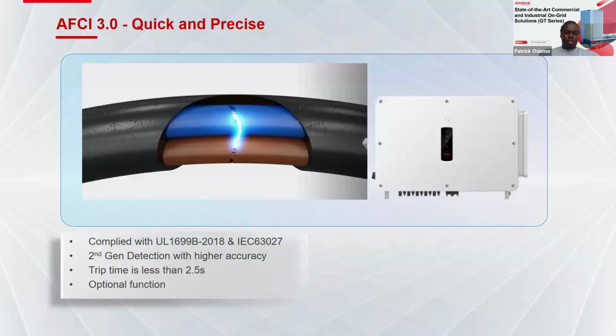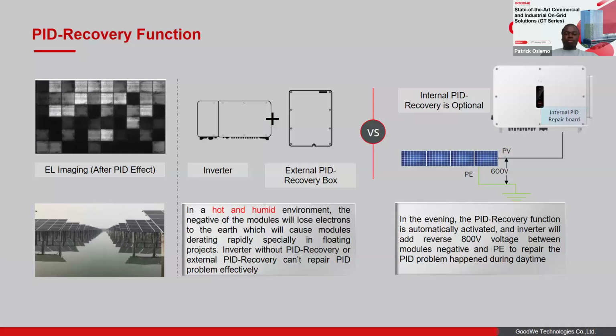Arc fault circuit interruption. Up to 200 meters, response time is very short. So be assured that in case you have loose connections on the roof, which lead to arcs, or even punctured cables on the roof, which lead to arcs, the inverter itself will sense these arcs up to 200 meters away, go to standby and alert you that we have arcs on your strings. So quick and precise response with the AFCI Arc Fault Circuit Interrupter version 3.0.